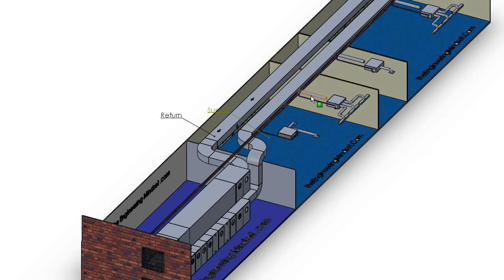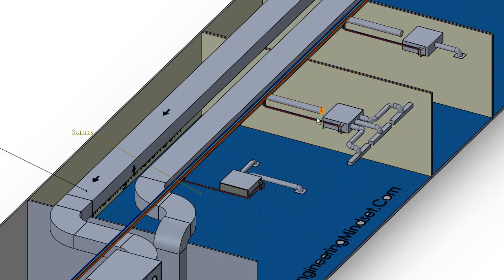So this fresh air is directed into the inlet of the fan coil unit, and it's usually not connected though, there's a gap in between. There is a reason for that which we'll look at later, and so that fresh air enters into the box. It gets sucked inside. Here's a fan, we'll have a look inside that shortly, and that air gets heated or cooled and pushed out through these diffusers into the space.